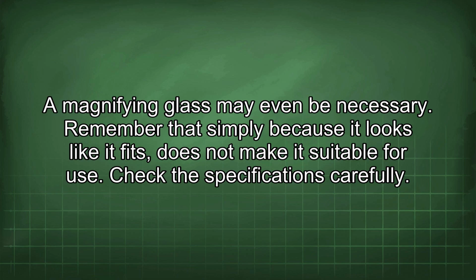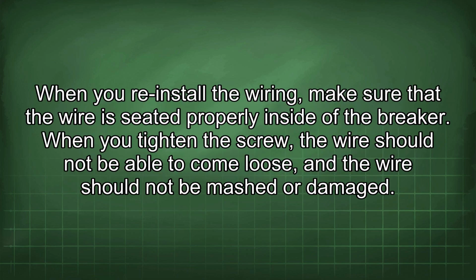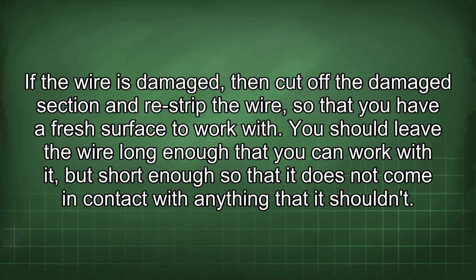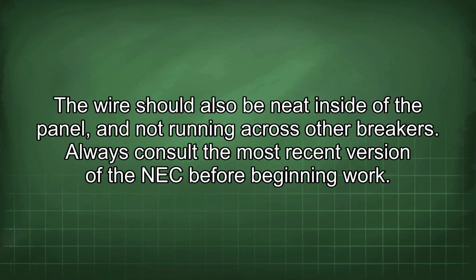Check the specifications carefully. When you reinstall the wiring, make sure that the wire is seated properly inside of the breaker. When you tighten the screw, the wire should not be able to come loose, and the wire should not be mashed or damaged. If the wire is damaged, then cut off the damaged section and re-strip the wire so that you have a fresh surface to work with. You should leave the wire long enough that you can work with it, but short enough so that it does not come in contact with anything that it shouldn't. The wire should also be neat inside of the panel and not running across other breakers. Always consult the most recent version of the NEC before beginning work.